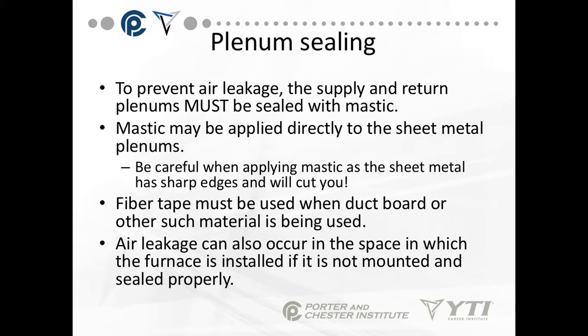Plenum sealing is required. To prevent air leakage, the supply and return plenums must be sealed with mastic. Mastic may be applied directly to the sheet metal of plenums, and you need to be careful when applying the mastic as the sheet metal has sharp edges and will cut you. Fiber tape must be used when duct board or other materials are being used.